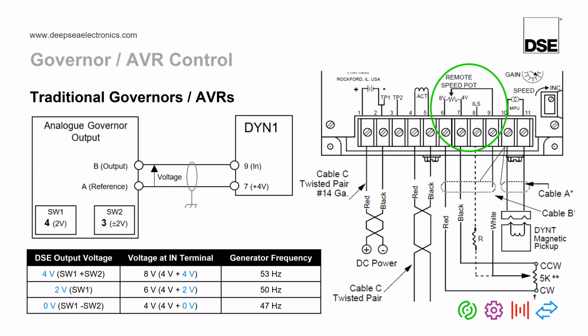And I mainly do this just so that you have a better idea of how to fault find if something goes wrong. For example, now you know that the DeepSea module is actually generating a DC voltage on its output. You might have a better idea how to fault find. For example, if you see 2 volts here on the DeepSea module's output, then in theory, you should see 2 volts across these 2 terminals on the governor or AVR. And that can help with fault finding, etc.